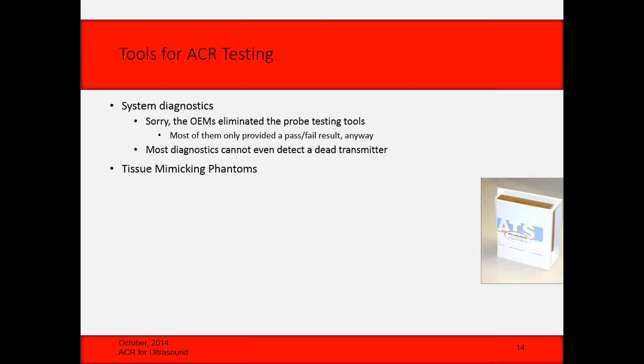So it's especially important in Doppler just because of the way that the Doppler beam is affected when there's either dead transmitters or dead elements or elements not working in the probe. So for example, phantoms became widely used back when the probes had a 182 millimeter aperture, these big giant linear probes that we used to have. And some of them actually had 32 elements, but when phantoms really became popular, they had 64 elements, that means that the width of each element is 2.8 millimeters. The linear probes now being commonly used for carotid studies have 192 elements and a 38 millimeter aperture, so it'll fit into your neck. And that means they're about 0.2 millimeters per element.